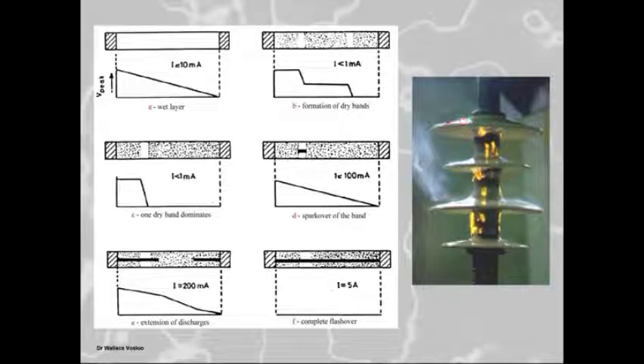So now all these pollution particles come on here and pre-deposit onto the surface. Then in the early morning you get some mist forming, or the humidity levels go beyond 75%, closer to 90%, and this forms an electrolytic layer on here. This electrolytic layer is conductive, and the resistance changes from hundreds of megohm down to maybe a megohm or so, and now currents start to flow over the surface.